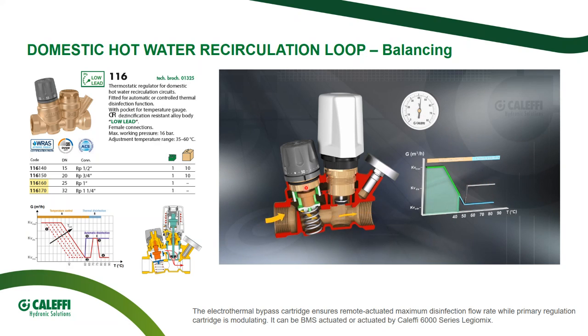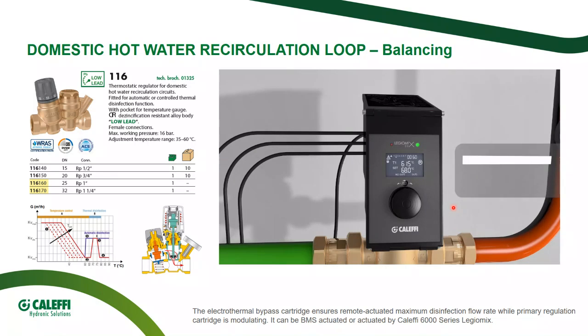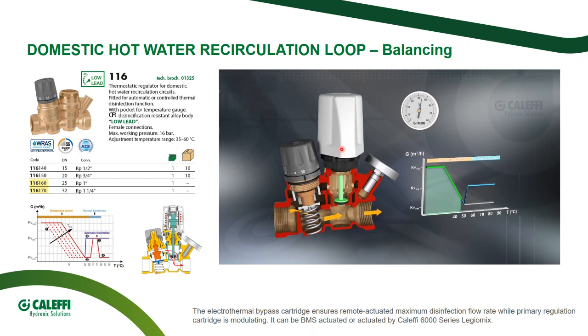For instance, this is a normal regulation, so my primary cartridge is reducing progressively the flow rate, but disinfection time has come, so the digital mixing valve is able to manage the opening or closing of the electrothermal bypass. So my flow rate will start increasing again for the period of time I decided, and the water will be at the right temperature we designed in order to carry out the thermal disinfection of the system.